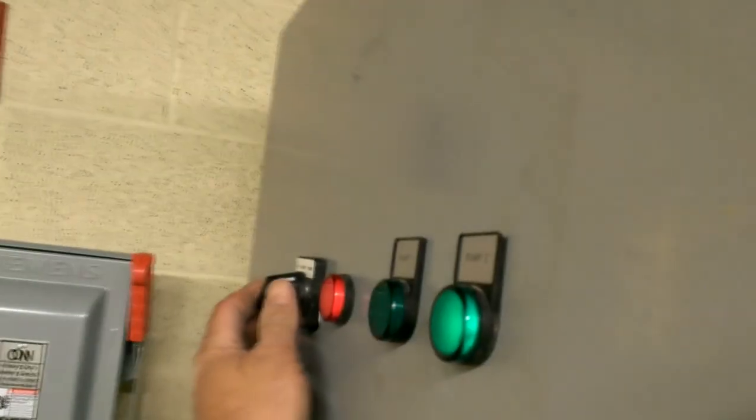It seems to be working good now. One more time I'm going to switch this over to pump one now. Watch the sequence. It stops the VFD. It's going to switch that relay.